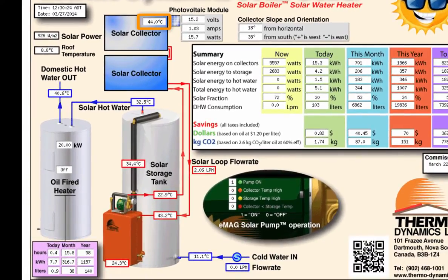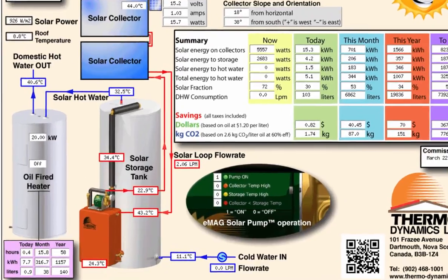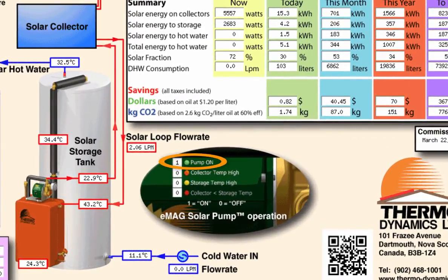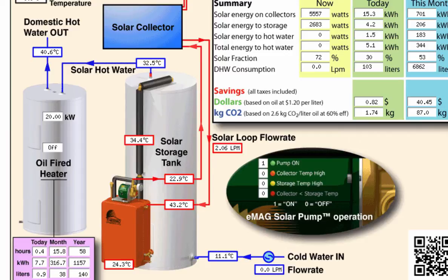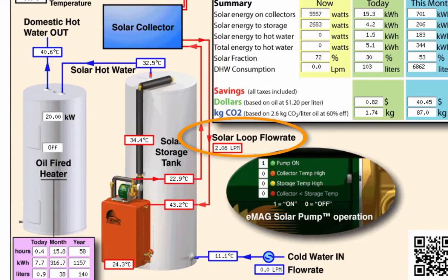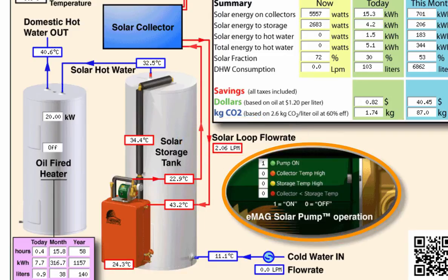When the collector temperature is hotter than the water at the bottom of the solar tank, as indicated here, the EMAG solar pump turns on and circulates heat transfer fluid from the solar collectors down to the heat exchanger inside the solar boiler module. The cooled heat transfer fluid then exits the solar boiler and returns to the solar collectors for reheating, continuing to recirculate through the solar loop as long as there is energy to be gained, as dictated by the EMAG solar pump controller.